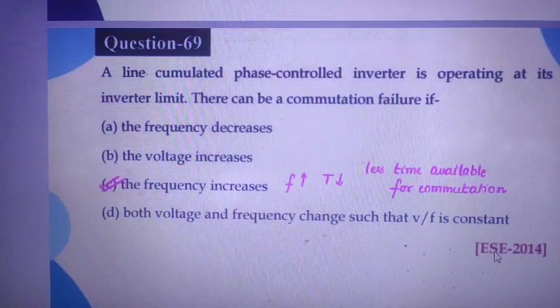A line commutated phase control inverter is operating at its inverter limit. Commutation failure happens. Generally commutation failure happens when less time is available. When less time is available for commutation, the commutation takes place very fast and there will be failure of the commutation. So slow commutations have less failure and fast commutations have more failure. So commutation failure happens because the commutation is very fast and has less time available, so the time period is less and frequency is high, so frequency increases.